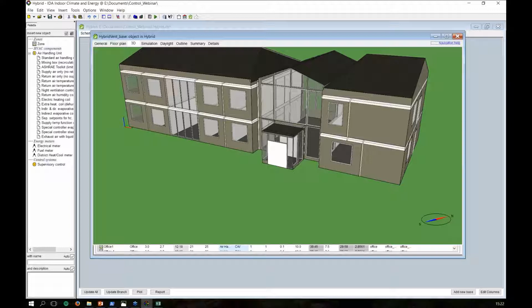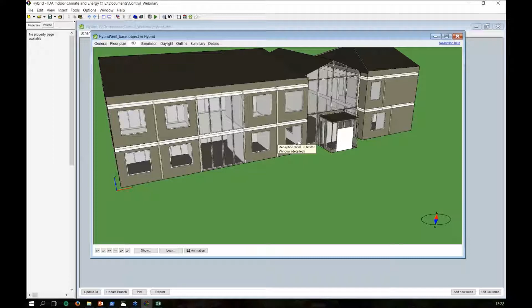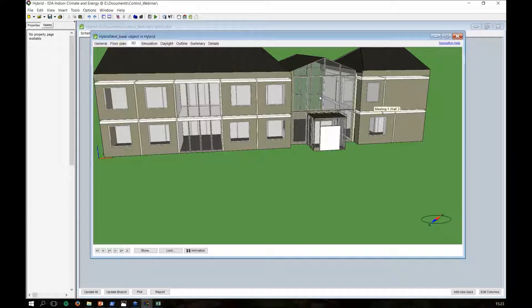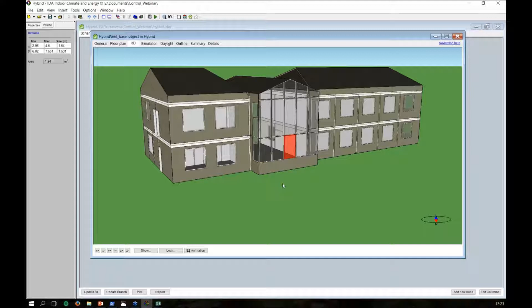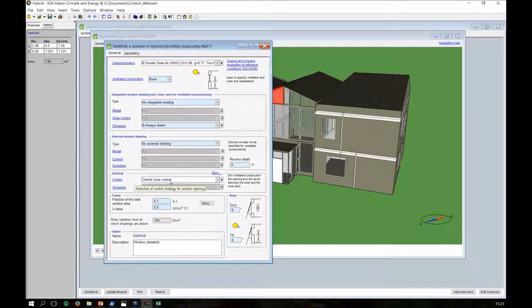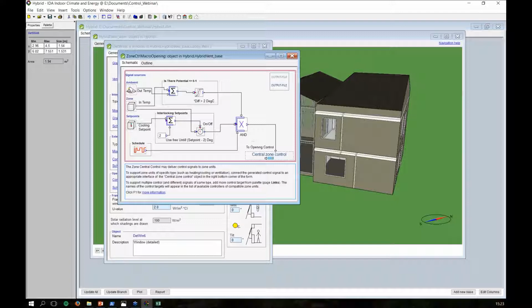So let's open our little office there. And here, to see the effect of ventilation and opening windows, I just removed the shades to have full solar load coming in. So what basically I will be doing is opening this upper window here and the lower window here to create this draft coming into the zone. And if I double click here, I'm controlling it through the zone control macro. So the zone control macro is opening those two windows. So let's see how it is controlling the opening of these windows.